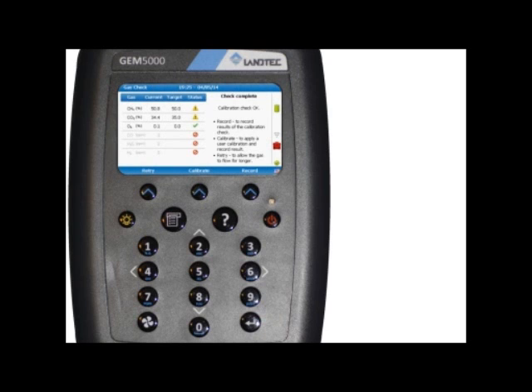After the timer is complete, the check complete message will appear, showing the 3 options available to select from. In this case, we're going to press the middle soft key to select calibrate. The unit is now calibrating. A calibration successful message will appear indicating all channels have been properly calibrated. Note that at this point the values again have not been stored into the memory, so do not turn off the gas at this point until the calibration values have been stored.